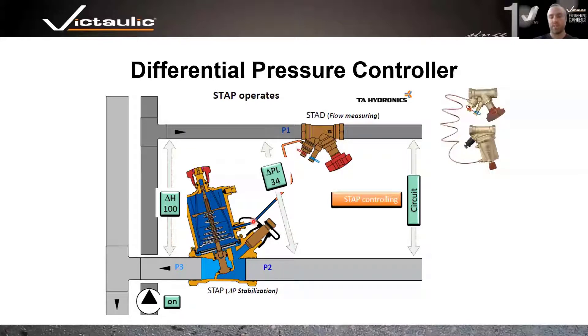We put these in two residences at the University of Calgary about six or seven years ago — one of the first projects in Alberta with these on the risers. We've all been in dorms and know they're among the worst buildings for heating and cooling, especially with students using window sills as refrigerators. By installing these valves in both buildings, they received zero complaints from residents about rooms being too hot or too cold. It's pretty substantial.